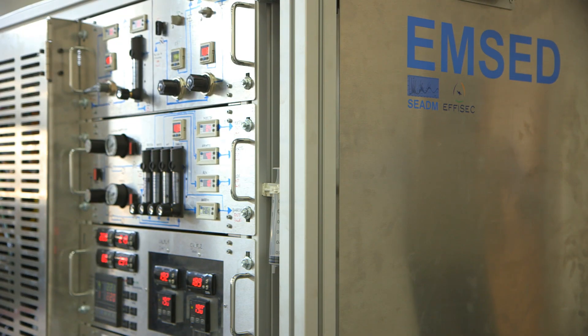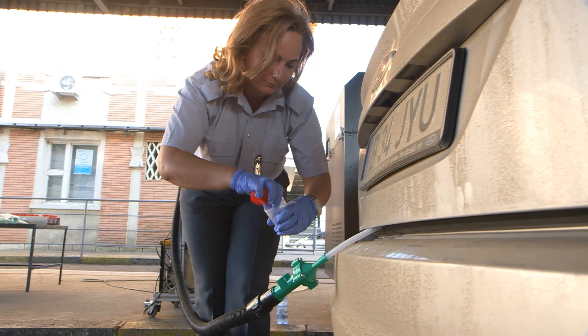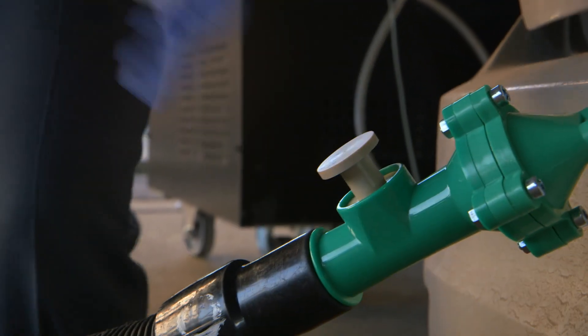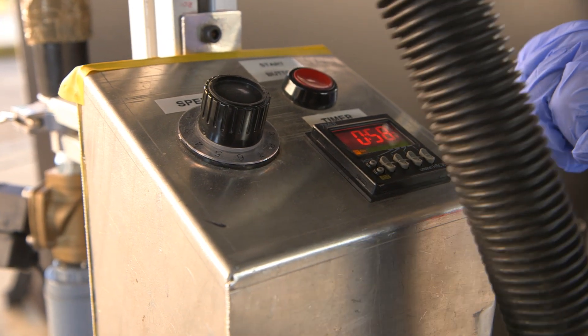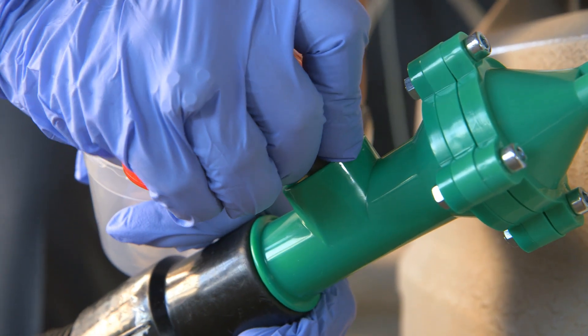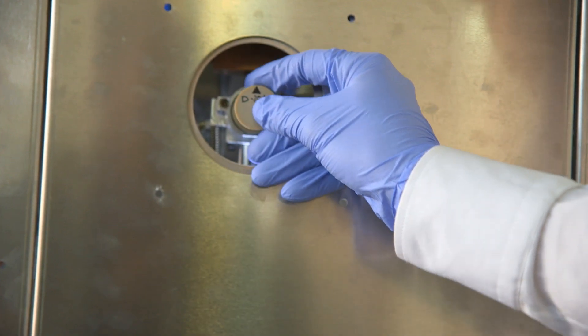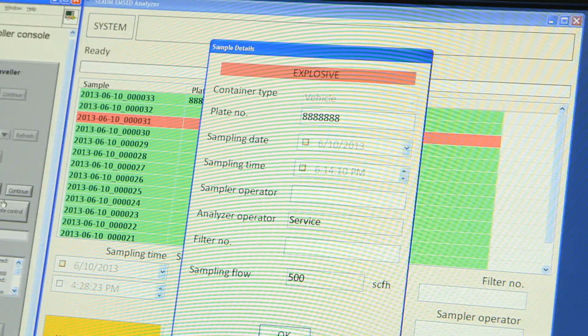EMSED has been developed by the Spanish SME SEADM. EMSED is a high-sensitivity and high-resolution explosive vapour detector based on mass spectrometry, differential mobility analysis, and low-flow GC. It is capable of detecting small amounts of explosives in the range of tens of picograms, making it perfectly suited for challenging applications like luggage and vehicle screening at security points. If vapours of explosives are present in the filter, the results are shown on the screen of the EMSED and then sent to the central site.